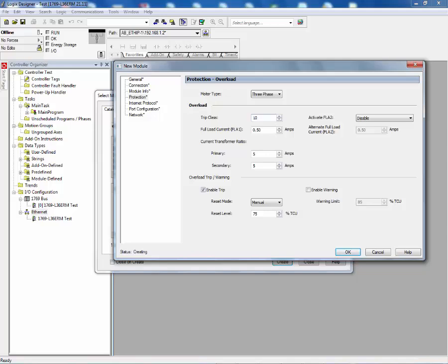And the user can select the trip class for his overload relay. In this example, we'll have a trip class of 10. And finally, we'll select our full load current rating for the electric motor. In this example, we have a one amp full load amp setting for our electric motor.